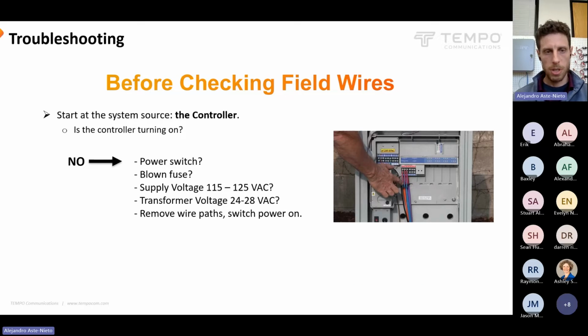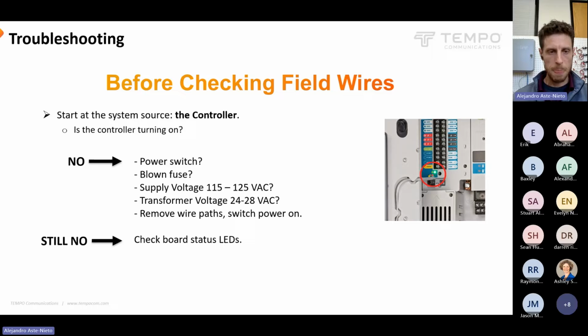Let's remove our wire paths and then switch the controller back on. If it's still not working and there's nothing connected to the controller, there's something happening in the controller that we need to know more about. There might be some LEDs to help us there. Otherwise, you might need to contact the manufacturer and see if they have any other tips. Otherwise, that controller might be damaged and might need some repair.